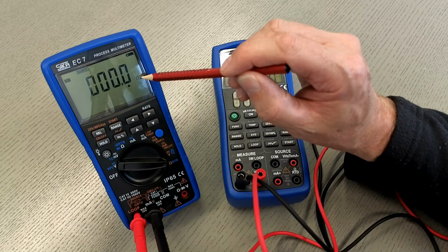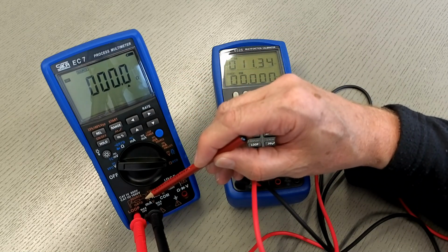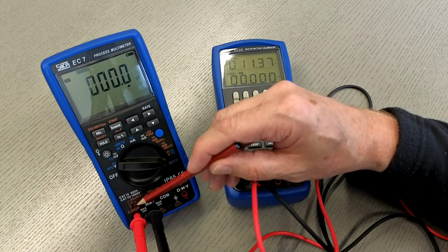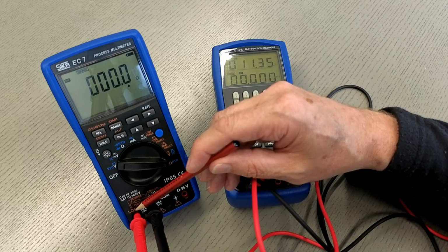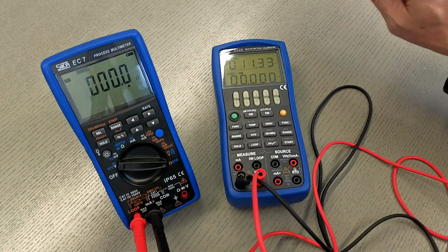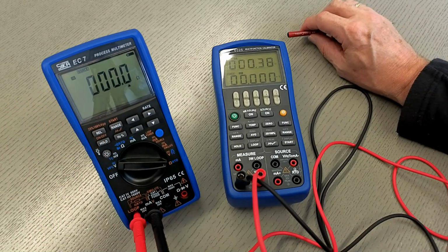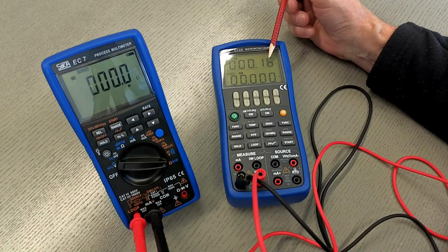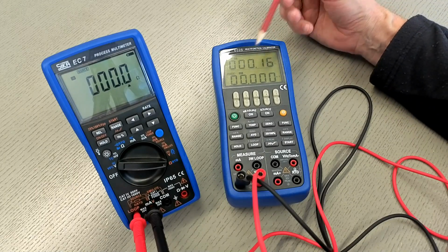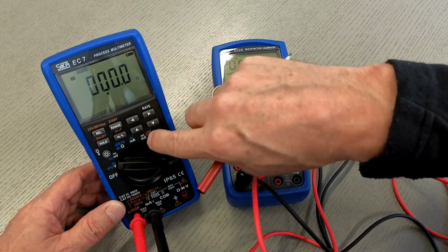And to have an ohm signal we have to connect the terminals on this position where we see ohms and RTD. So that means on terminal number 1 and terminal number 2. So I'd like to generate 0 ohms. On my instrument I also see 0.18 ohm. Everything fine.